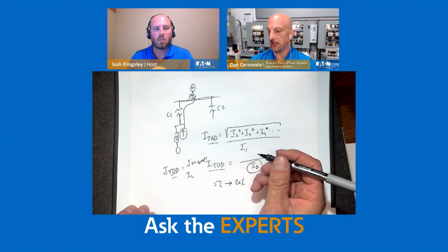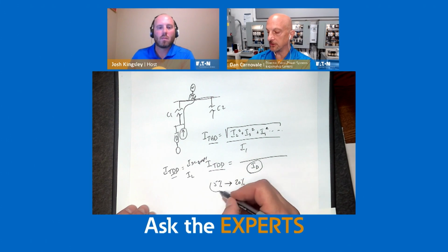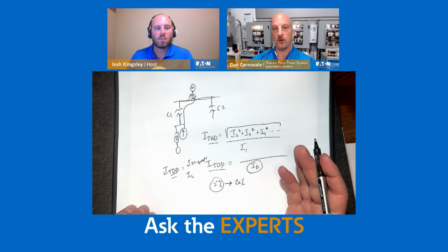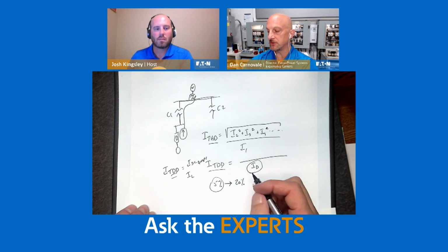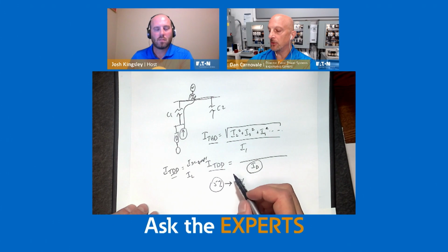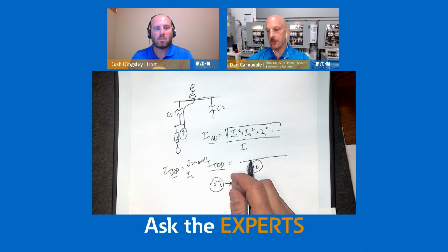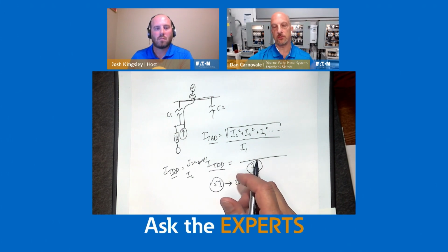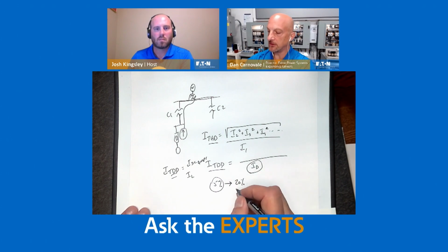Now, if you look at an 18 pulse drive, most of the time you're going to be below that 5%. So that's where, going back, Josh, to the original questions that we talked about, you don't even have to deal with it at that point because it already, quote unquote, complies with that. But when people say comply, that's a little bit of an interesting thing, because the way the standard is written, you only comply at the point of common coupling. So people sometimes use it down in the system, and we could talk about that more if you want.